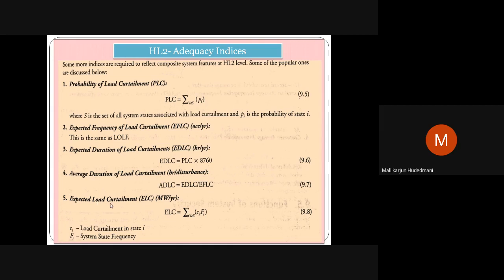Expected load curtailment, ELC, in megawatt-years, represents the load curtailment due to generation side or transmission side jointly. It is the sum over all states I belonging to S of CI into FI, where CI is the load curtailment in state I and FI is the system state frequency, meaning the frequency of occurrence of state I where load curtailment is possible. This relates to frequency and duration based assessment of reliability.